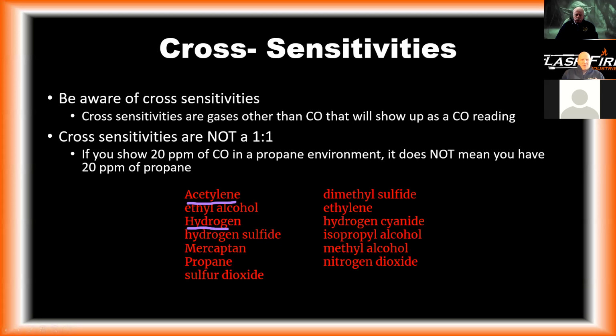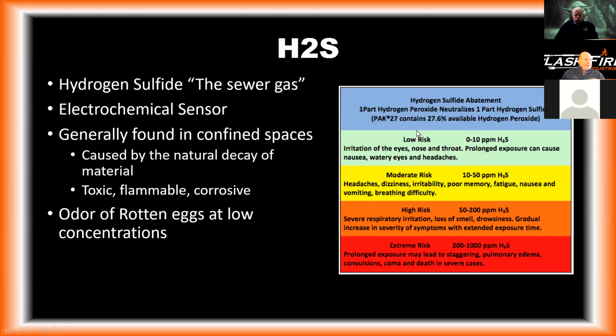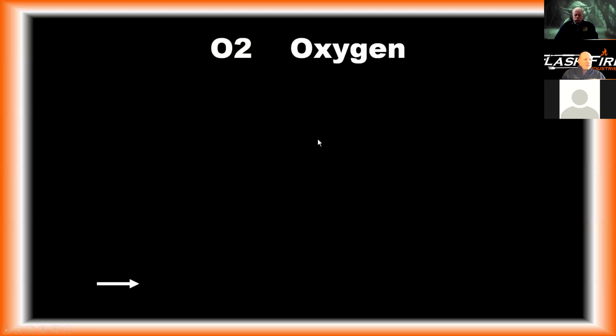Hydrogen is a very common one, especially with all these batteries charging now. You may have low levels of hydrogen setting off the CO meter if the battery is not charging properly. So just be aware that cross sensitivities do exist, and if you really cannot figure out what's setting off your CO alarm, then consider something in the cross sensitivity realm of things. H2S, the sewer gas, hydrogen sulfide. Again, electrochemical sensor, generally found in confined space. Toxicity is the main hazard, but it is a flammable and corrosive gas as well.